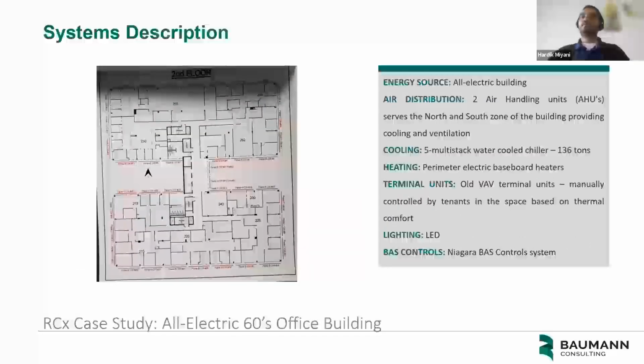So, giving a background about the system description. This is an all electric building, which means there is no use of natural gas at all, be it for heating, hot water or cooking. The building has 2 air handling units that serve the north and south zones of the building, providing cooling and ventilation to the space. The cooling is provided by 5 multi-stack water cooled chillers with a total cooling capacity of 136 tons. The heating is provided by perimeter electric baseboard heaters, as you can see in the image on the left. All the ones colored in red are the perimeter electric baseboard heaters that are serving the entire building.